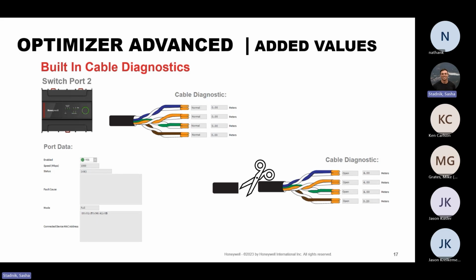Our controller, the CIPer 30 and the advanced controller, are the only ones in the portfolio that have in Niagara something we call chip diagnostics or cable diagnostics. It's on the chipset, and it will tell you via Niagara how many meters down the stream that Cat5 or Cat6 cable you lose communication. It's easier, still not 100%, but at least you know where to start. So if you have a controller down the stream, you go into the layouts, and Niagara tells you it's 1,000 meters down. Then you look at the layouts and say, okay, that's probably the 5th floor. So you go to the 5th floor and start to ping, not all the floors. This is so important, and people like it so much.